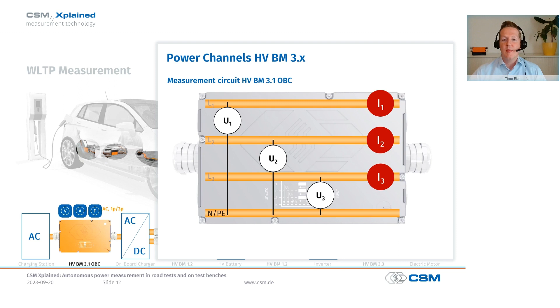The currents are, of course, measured again by means of fully compensated shunt modules directly in the three respective phases. In this way, the HVBM 3.1 OBC can relatively easily calculate the power characteristics directly from the raw data without having to use a trick like the two-wattmeter method.